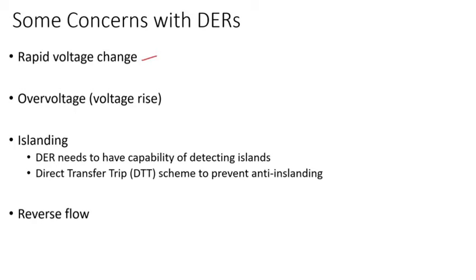You have over-voltage and voltage rise, which I'll talk about in detail. There's voltage rise from the generator back to the feeder, and islanding issues — when you lose the utility system, the DER needs to have the capability of detecting islands.